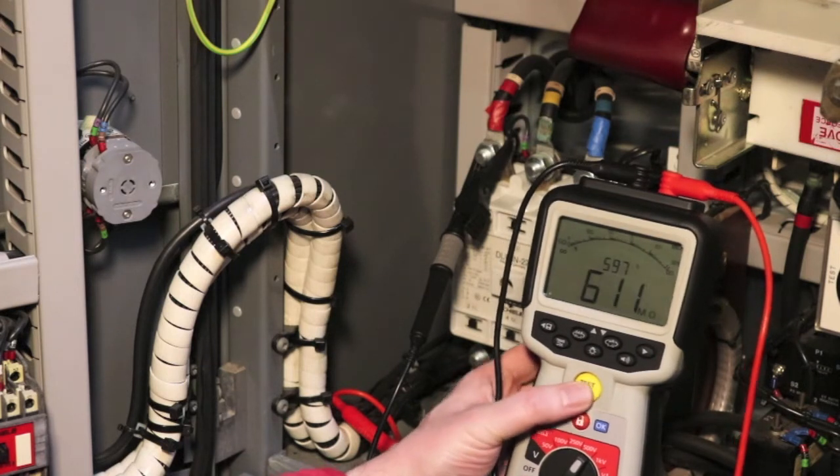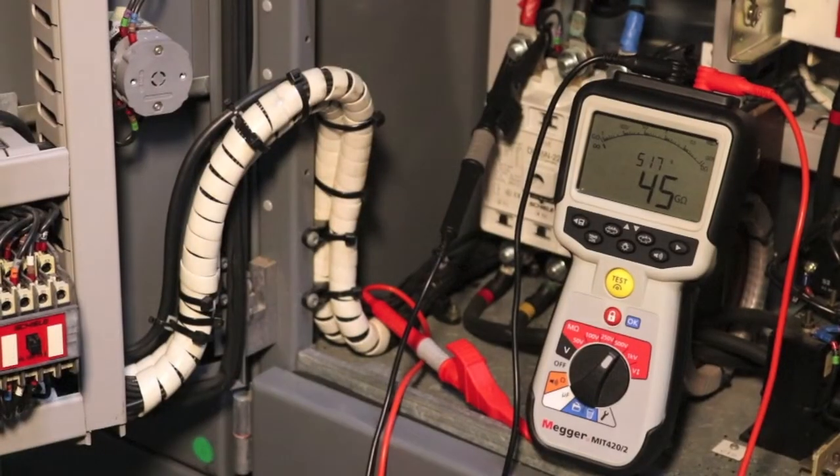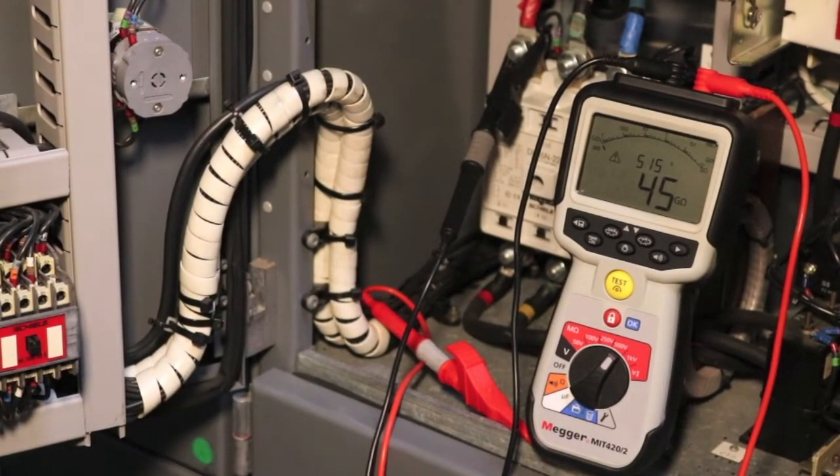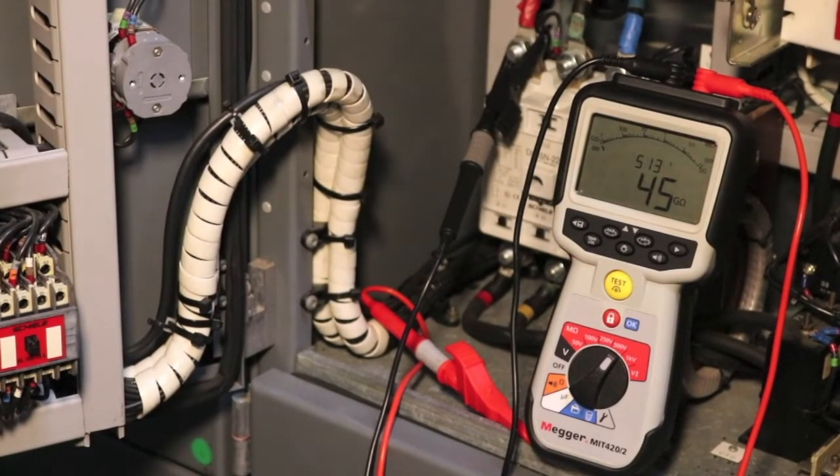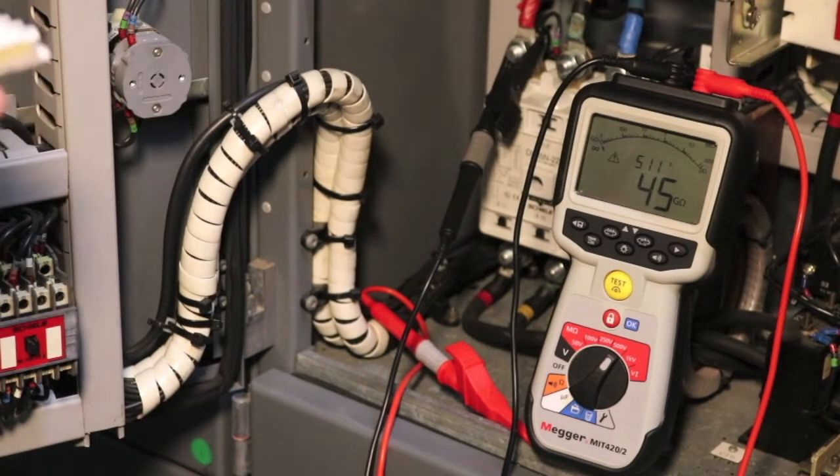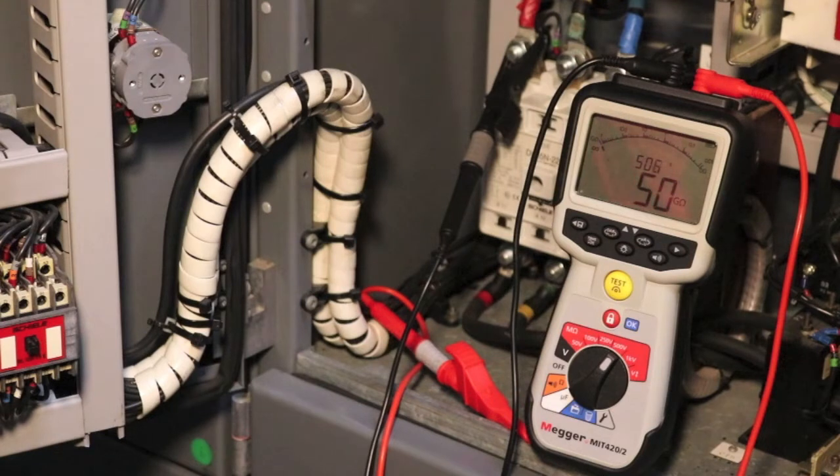So that's the polarisation index test started now. You can see it's got up to 45 gig ohms already. I will take a reading every 60 seconds and record that so I can then plot the insulation curve over the whole 10 minutes of the test.